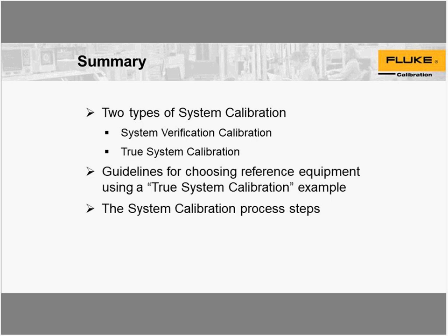Roger, if the as-found data is within tolerance, will you still recalculate new coefficients? Yes, we will still do that, even if they're in tolerance. The case where we don't is if the error is less than our stated uncertainties for our reference equipment. If the error is that small, then there's no adjustment needed at that point.